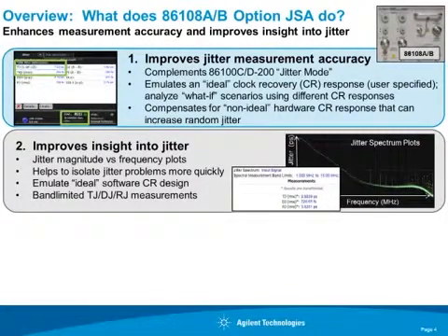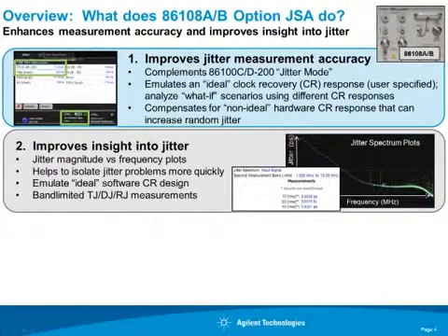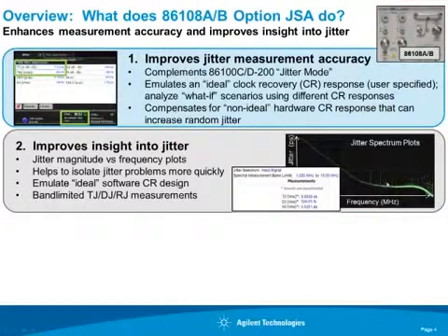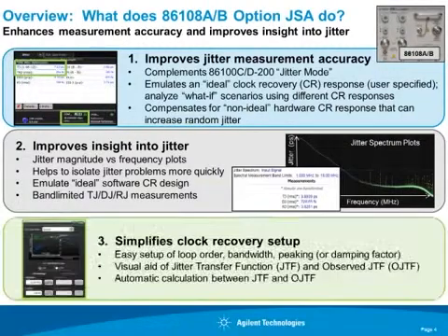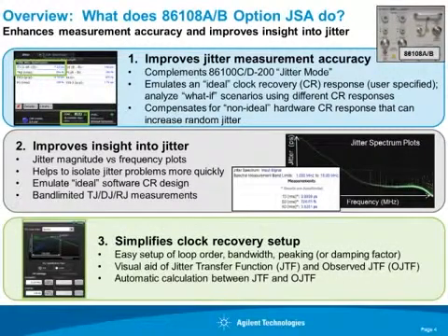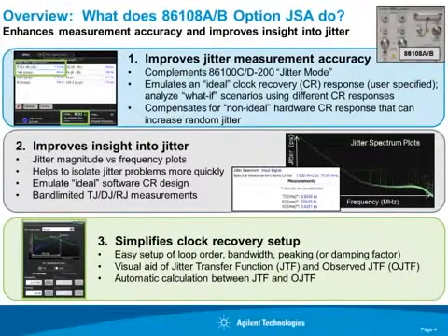For example, you'd be able to determine whether an increase in jitter was due to low-frequency jitter, which is typically generated by phase noise from your reference clock. It also makes it a lot easier to configure and set up your clock recovery, as you'll see shortly in the demo.